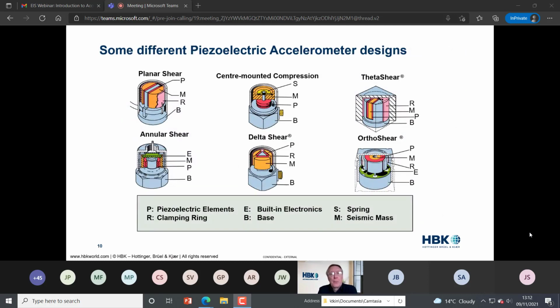Here are some current practical configurations of accelerometers, and you can see that they all have some form of central post onto which the discs of ceramic, which are shown here in red, are bonded. Then we've got the seismic masses on either side, and then there is a clamping ring all the way around to hold the assembly together. Now, as you'll notice, 5 of these 6 designs are shear of various types. Only one here is compression. Compression accelerometers are not in such large use these days as shear types. The one on the bottom right here, the ortho shear, that is a triaxial design.